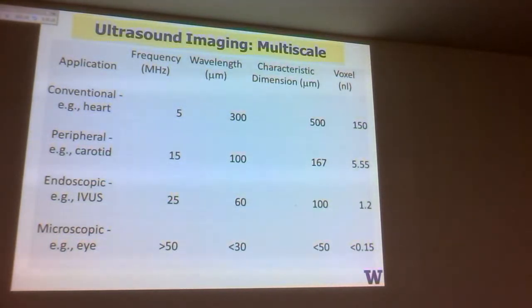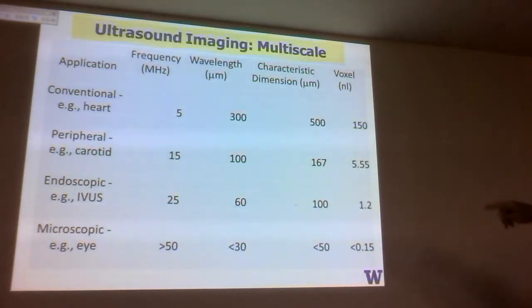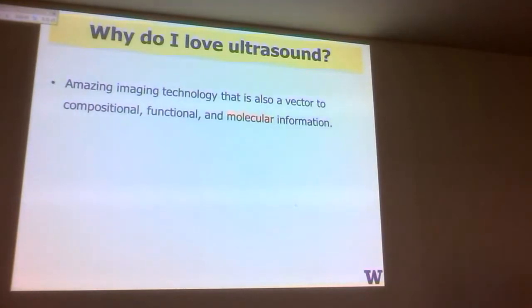Within the ultrasound industry it's usually called small parts. I always like that. At 15 megahertz, the wavelength is 100 micron. Characteristic dimension, you're down around 5 nanoliters then. The endoscope and IVUS system I'll show you is 25 to 40 megahertz, and 60 micron resolution, you get about a nanoliter. When you get up to around 50 megahertz, and especially on the order of about 100 megahertz, you get well sub-nanoliter sample volumes and resolutions in the tens of microns, so 20, 30 microns. Again, you trade this off for the particular application, and that trade-off is fundamentally the probe, the transducer, that you build.